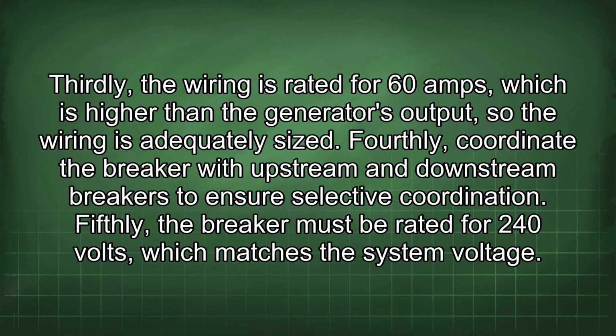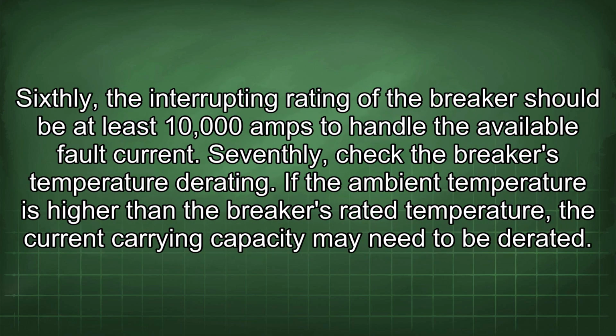Fifthly, the breaker must be rated for 240 volts, which matches the system voltage. Sixthly, the interrupting rating of the breaker should be at least 10,000 amps to handle the available fault current. Seventhly, check the breaker's temperature rating. If the ambient temperature is higher than the breaker's rated temperature, the current carrying capacity may need to be derated.